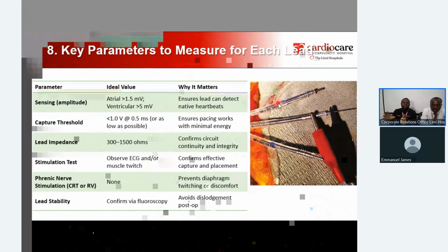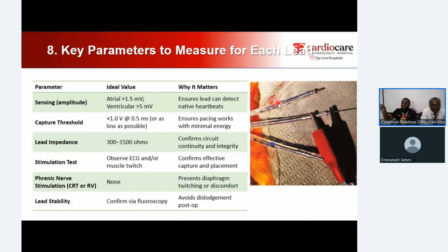That's where we get to see the values of the P wave, the values of the R wave. It's very important to check this. You don't want to connect to the pacemaker and before you get one year down, the pacemaker is dead because you did not get a good placement. So you need to test. You must test it on the computer and be sure it's good before you connect the pacemaker. No rushing to do anything.